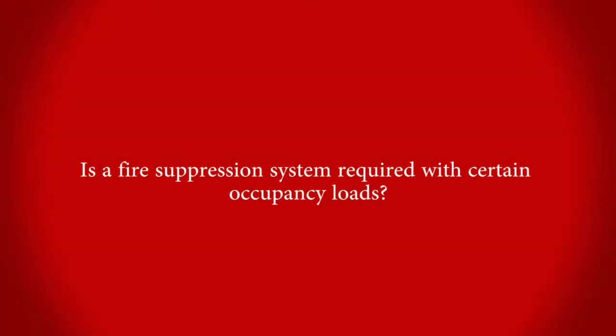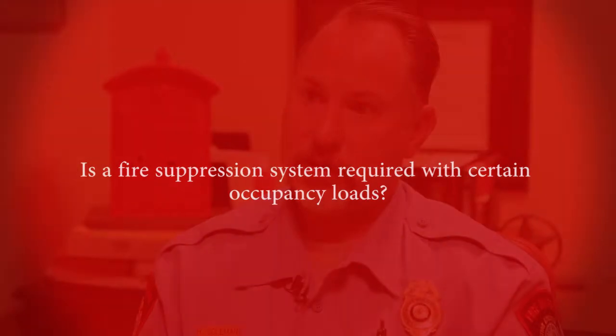The occupant load of the building typically determines whether or not a fire alarm system or a sprinkler system is required. There's a lot of misnomers that we seem to think that if our building has sprinklers, we can add more people, or we can do certain things to our buildings. That's not true. The square footage requirements and the capacity width requirements all stay the same.